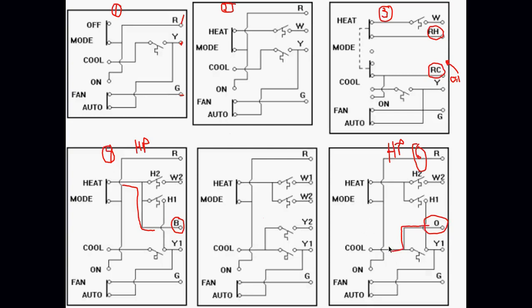So 6 would be more of a northern thing. Well, now it's becoming more standard, okay? I mean, I'm in the south, and my heat pump is set up to have an O terminal. But it used to be that you would see 4 down in the southern climates more because cooling is our default, and 6 you would see in the northern climates. But now O's become more of the standard. Make sense? Yep.